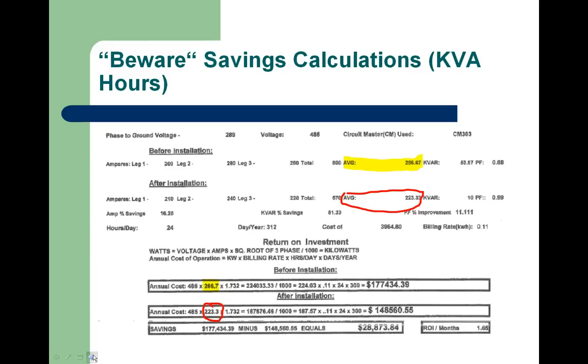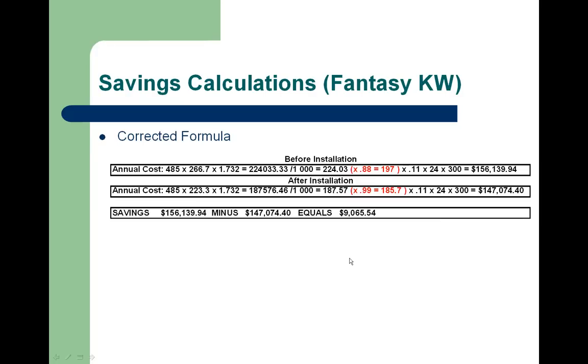Now, as we get on to the next slide, what I've done is I've taken the same values that they used, and I've actually put in the power factor that they had. So the original value of $177,000 cost really would have only been $156,000. Their cost after the kVAR, I think they had 148, calculates to about $147,000. So in a case like this, at very best, the savings could be as much as $9,000. Now, this is about 6% of the total kilowatts. The 6% in I squared R savings is a number I've heard used a number of times. It's a fairly large percentage. It's unlikely to happen unless you have heavily loaded cables at great distances.